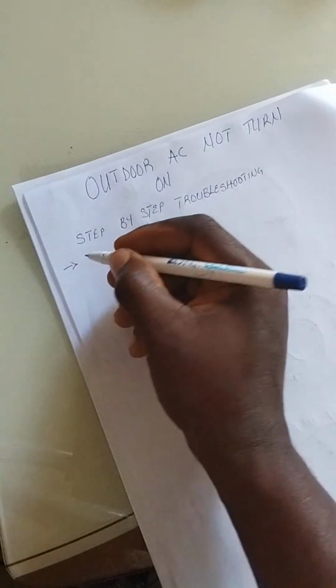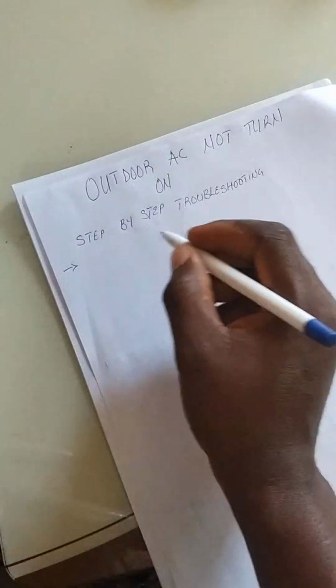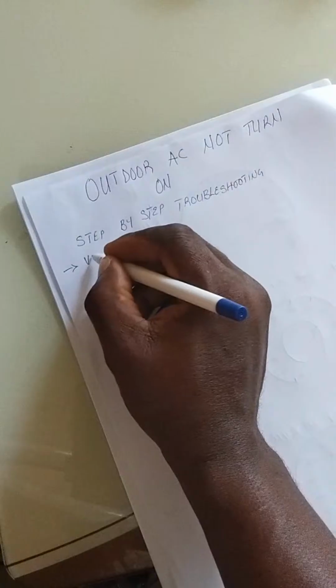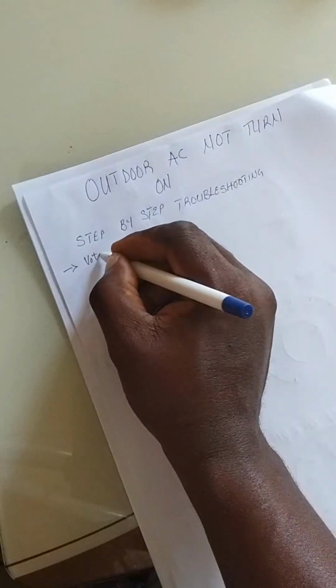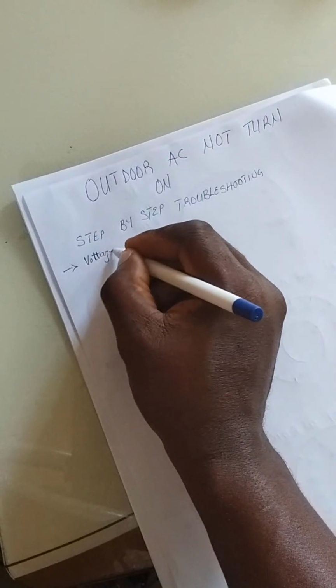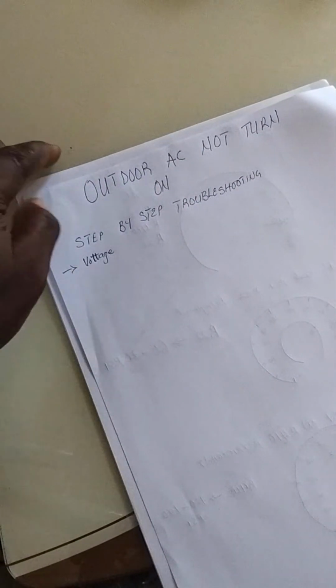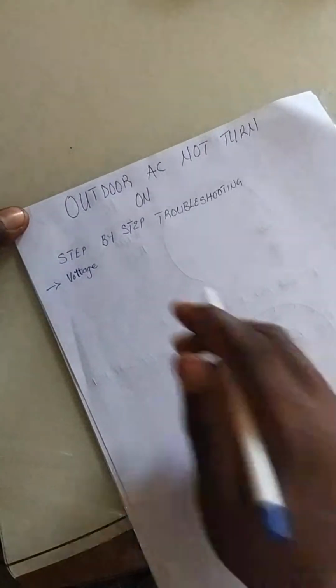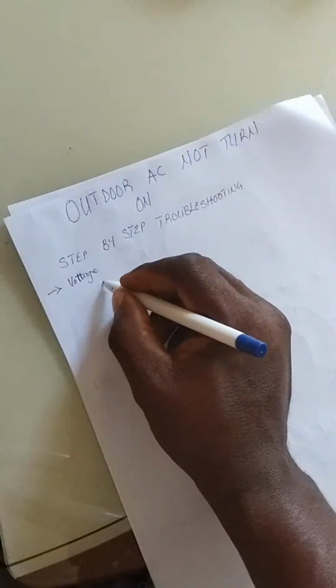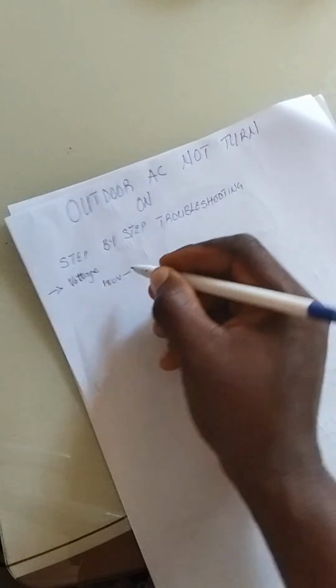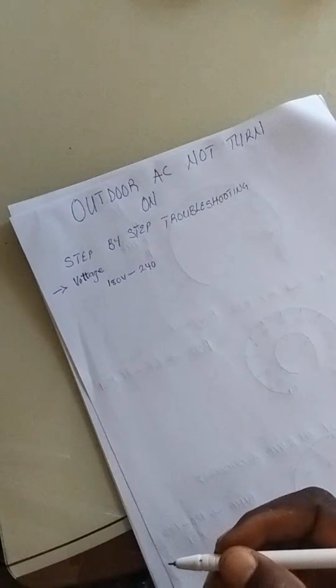Okay, we got this. Step number 1, voltage. That is one of the factors that could stop an AC outdoor system from turning on. One is the voltage. So how does voltage actually affect an outdoor system not to turn on?